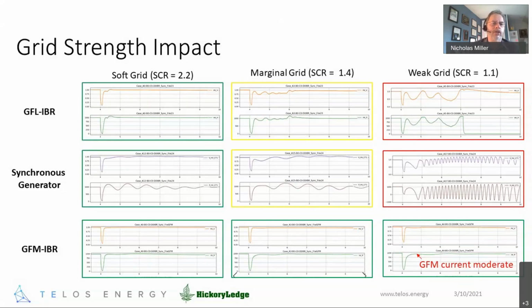It has a short circuit ratio of 2.2. The center column is what we've called the marginal grid, marginal because the stability of our available technologies is marginal, with a short circuit ratio of 1.4. Then we've gone to a weak grid with a short circuit ratio of 1.1, and we went quite a bit below that with grid forming inverters.